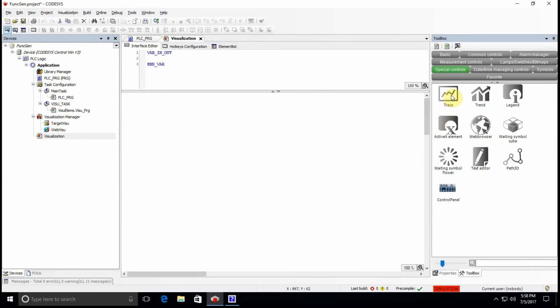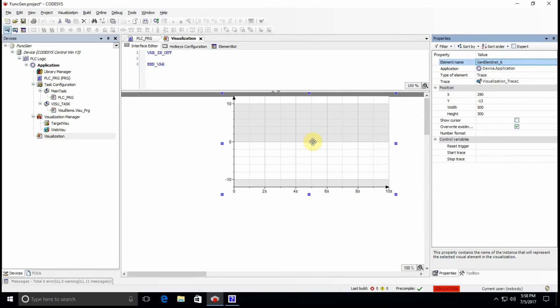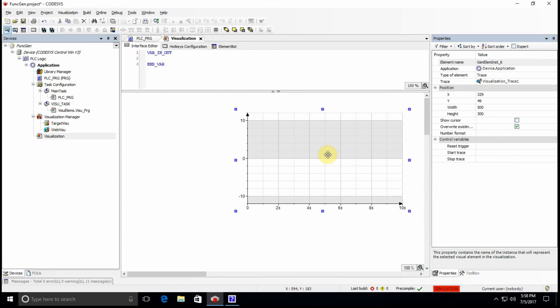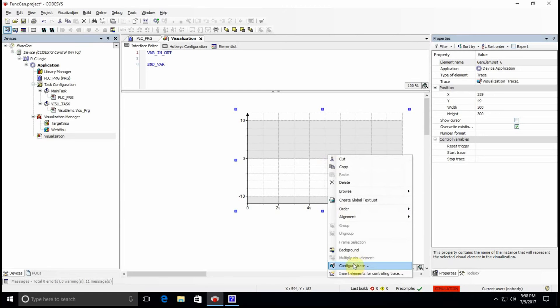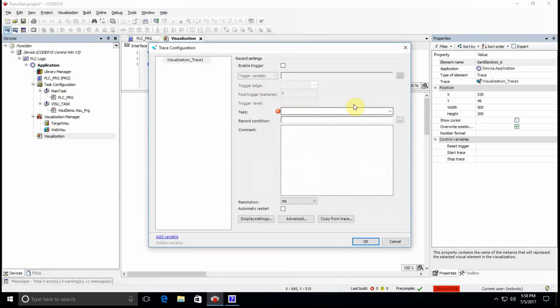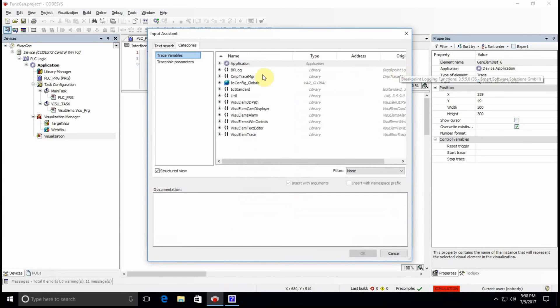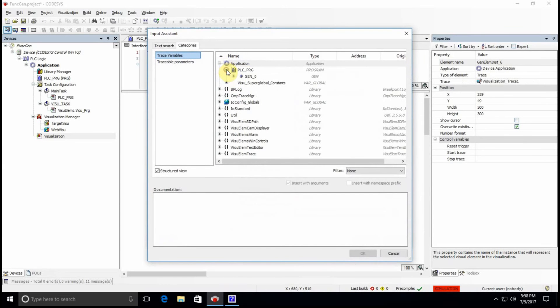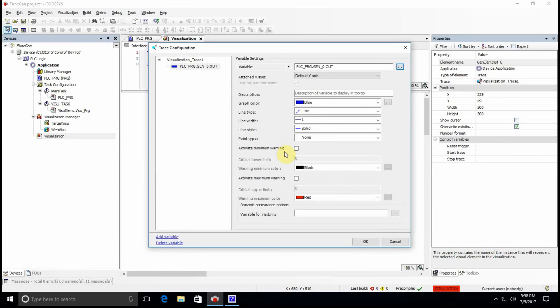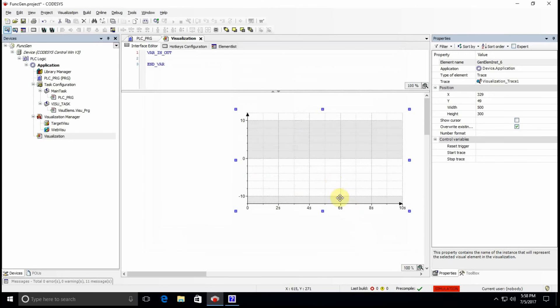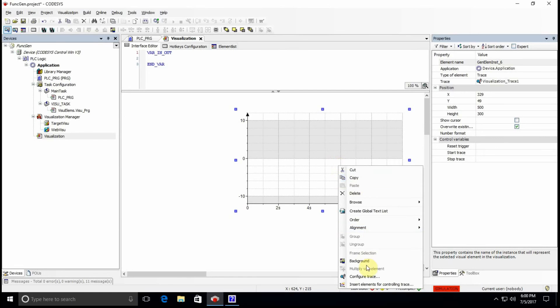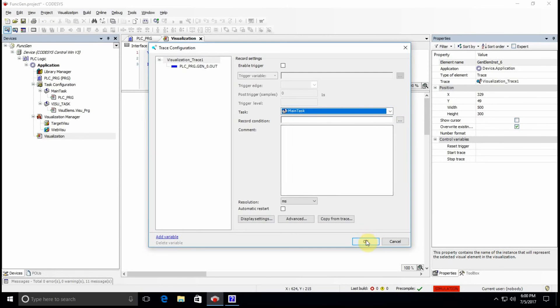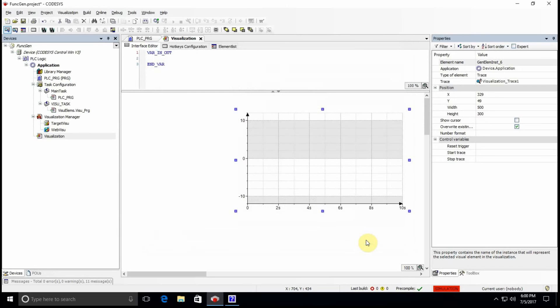I will try to use as few variables as possible. I will refer directly to gen_0.inputs and .outputs. As a result, I go directly to visualization. Here I use one trace element to display the output of the function. To have it, I go to configure trace, I add one variable, and the variable here is within my PLC_PRG gen_0 and it's the output. I keep the files like this. So for trace I have added the variable. I just want to determine which task it belongs to, I select the main task and here we go, it will be displayed on this graph.